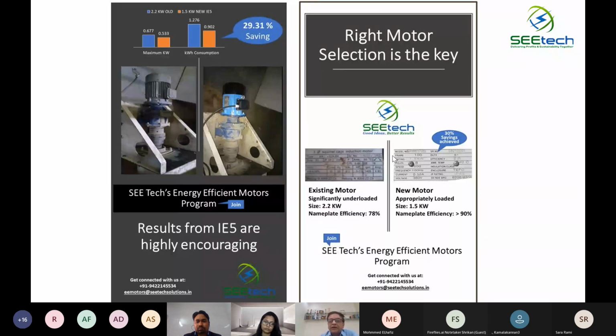But the actual savings are pretty high. So why are these savings so high? Because at lower loading, motor efficiencies are extremely poor, particularly for IE1 or IE2 motors. The part load efficiencies are very, very poor, whereas this IE5 motor has very good part load performance characteristics. So we need to get much, much deeper into every energy efficient retrofit technology.